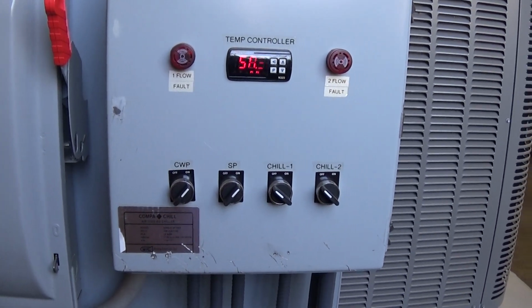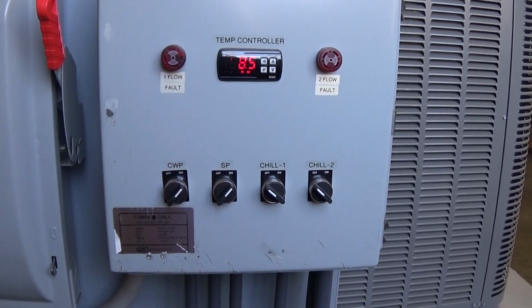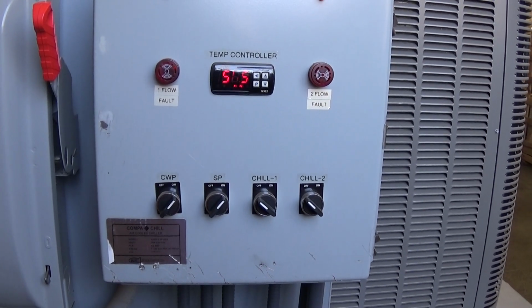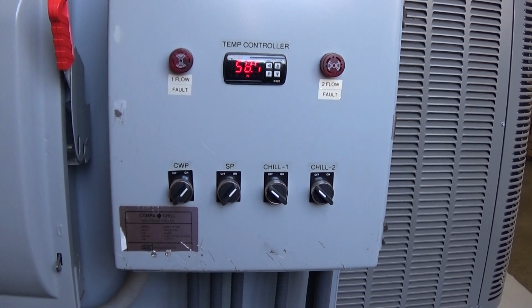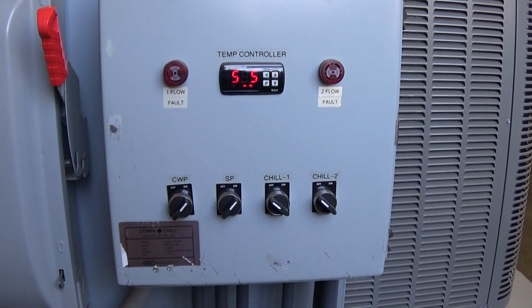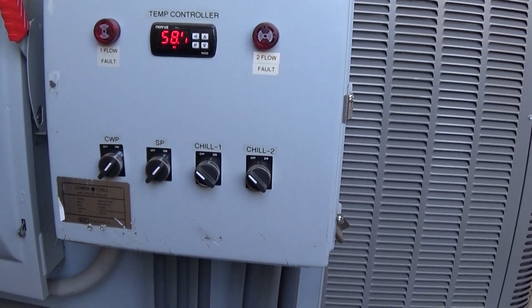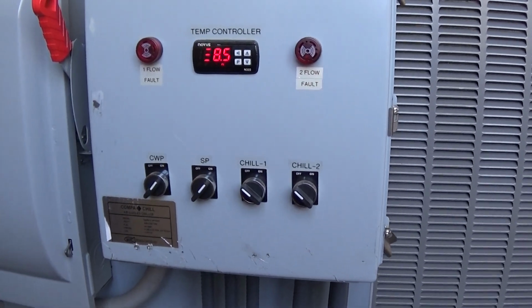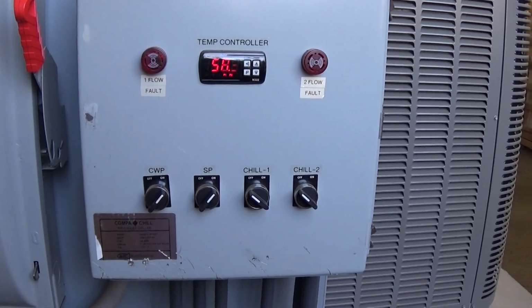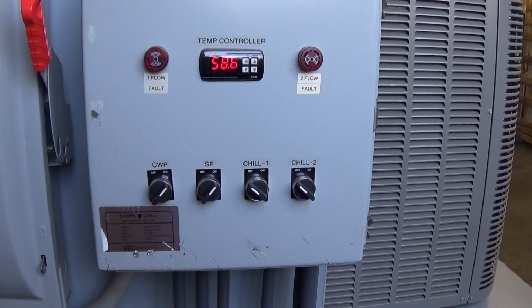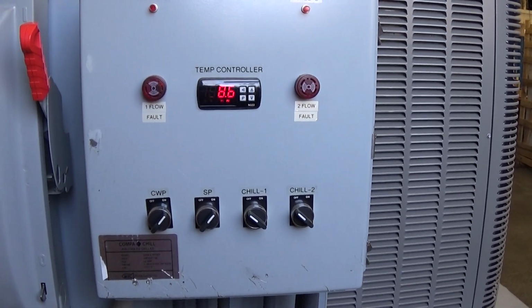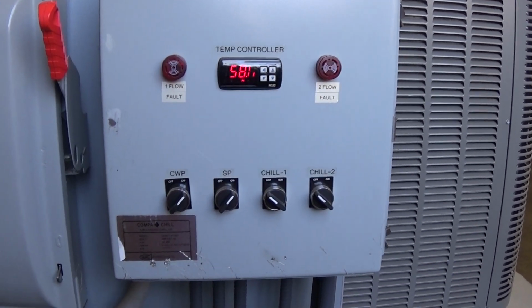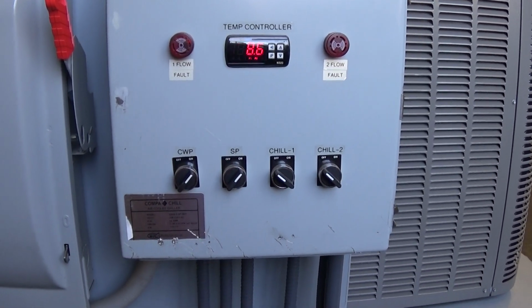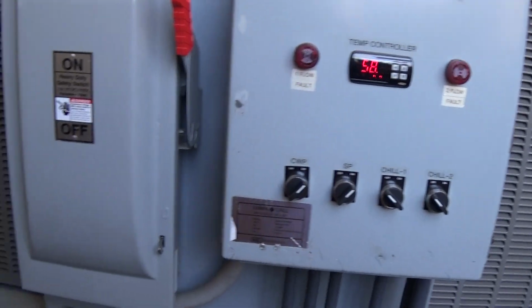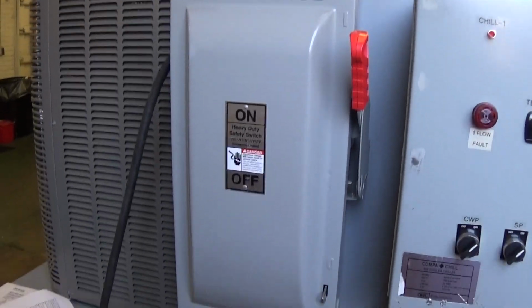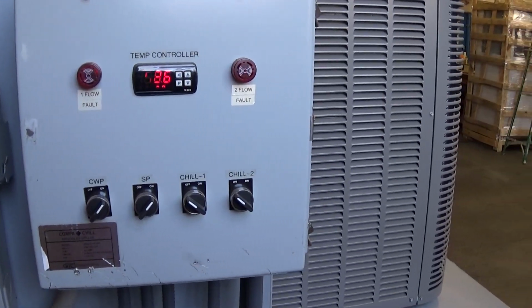This system, the manual implies otherwise, but we really don't want you running an R410A refrigerant system like this much below 25 Fahrenheit. On that issue, run it at the warmest you can get away with without sacrificing or hurting your process. The colder the set point, the harder the compressors have to work, as with any chiller. So we're going to run circuit 1 for a while, and then we'll run circuit 2 later on.